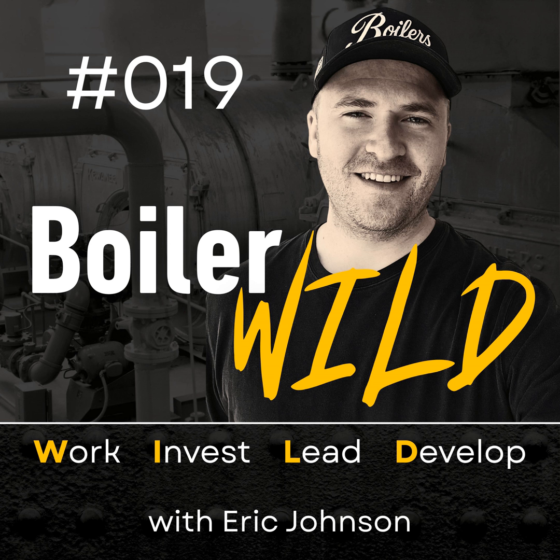You can find this graph on Lochinvar's website if you want to look at it, but every manufacturer has a similar graph. And it essentially shows you that a boiler that is 99% efficient is 99% efficient at 5% firing rate when the return water temperature is 73 degrees. So how many hydronic heating systems do you know with a return water temperature that's 73 degrees? I don't think I've seen any. They're out there, but very, very rare. And normally that's a special application. You cannot do much heating with 73 degree water.